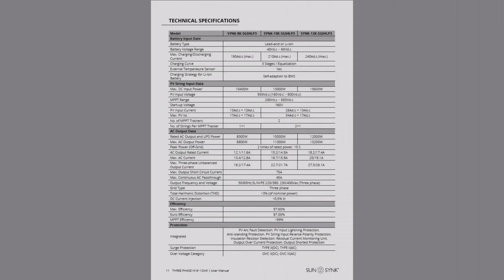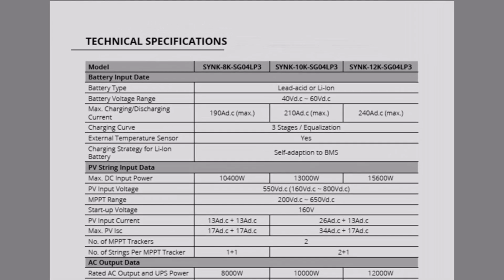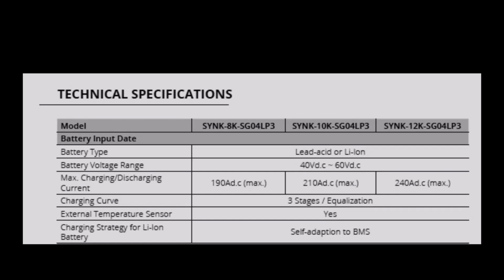Okay, so let's have a look at the technical specifications, and we are going to look at the 12 kVA model. This first line, which says battery type, shows that you can use lead acid batteries or lithium ion batteries. Very few people would use lead acid batteries these days. The battery voltage range: although the battery is a 48 volt battery and that's its optimum voltage, it can operate between 40 and 60 volts DC, and nothing untoward will happen.